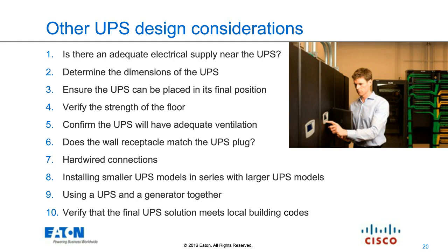But there are considerations. UPSs and generators work well together if they are planned to work well together. So if there's a generator already on site, that's something that my team needs to be aware of when we're having these conversations, because that's going to limit the amount of UPS that you can actually put on the generator and expect a good, clean solution. And, of course, all of this is going to have to fit within all of the local and state and federal electrical codes. So making sure that you have a quality contractor when you start these projects will make sure that you don't run into binds later in regards to coding problems.